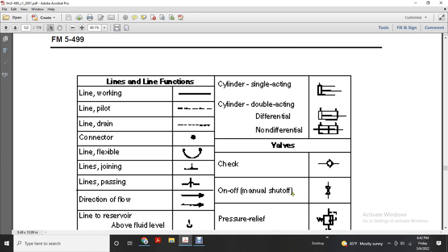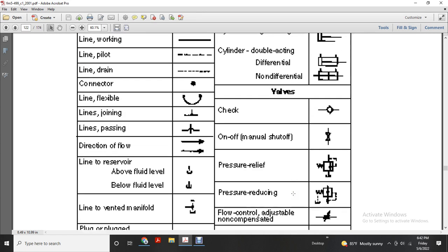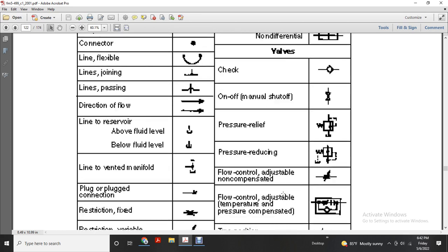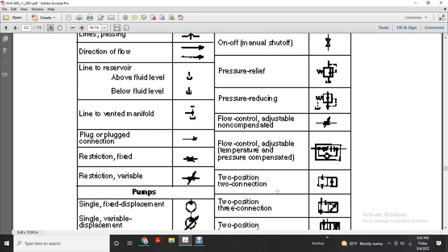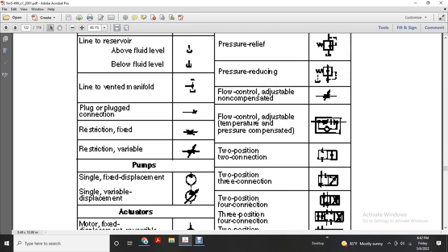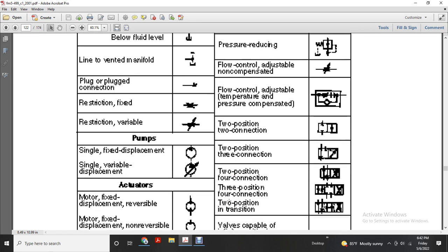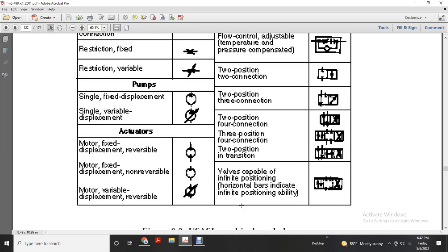check valve, on and off, manual shut off, pressure relief, pressure reducing, relief shows it going to a reservoir and in the open position, flow control adjustable non-compensated, flow control adjustable, temperature, temperature and pressure compensated, two position three connection, two position four connections, three position four connection, two position transition. Valves capable of infinite positions, horizontal bars indicate infinite position ability.